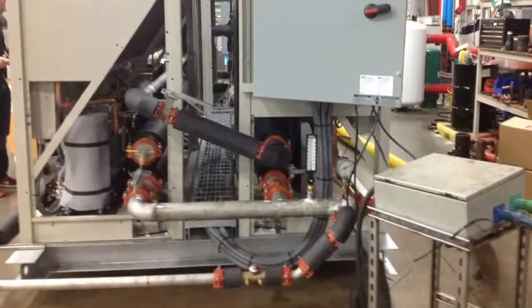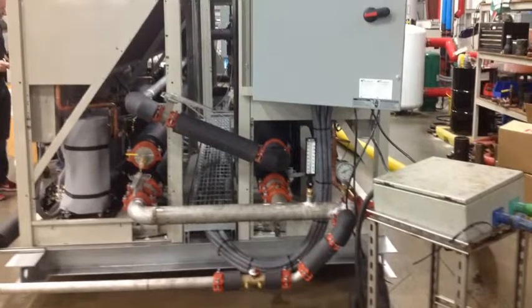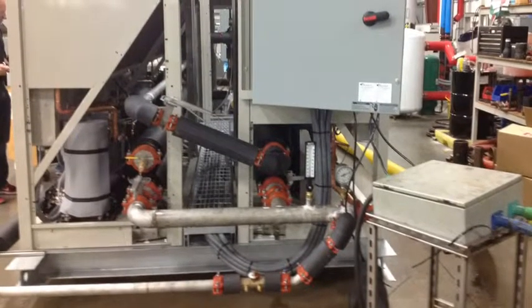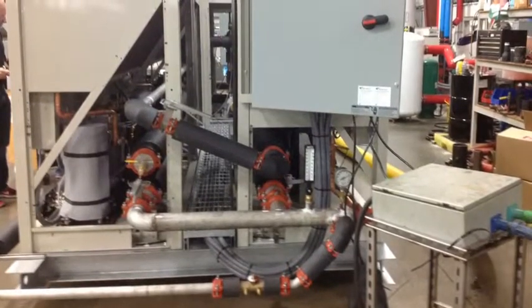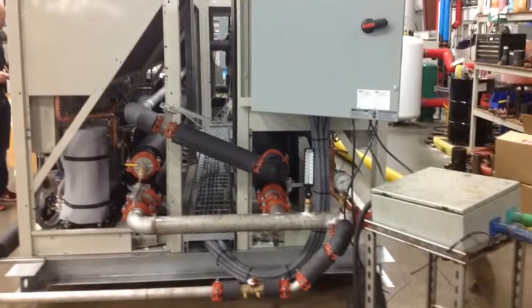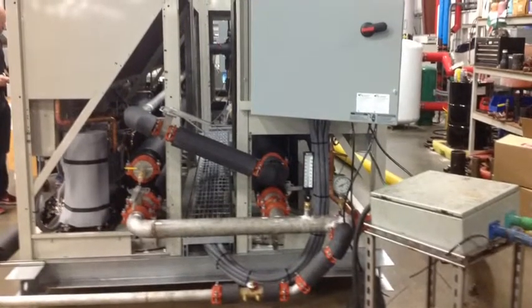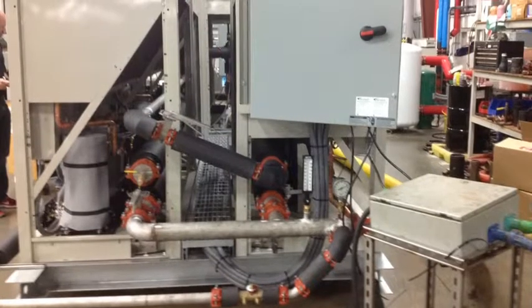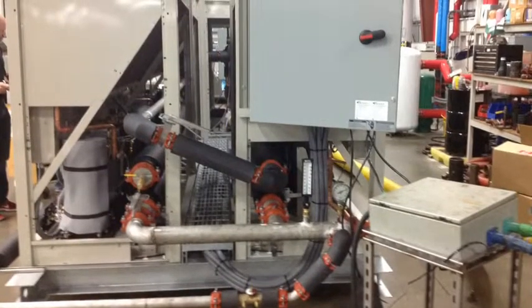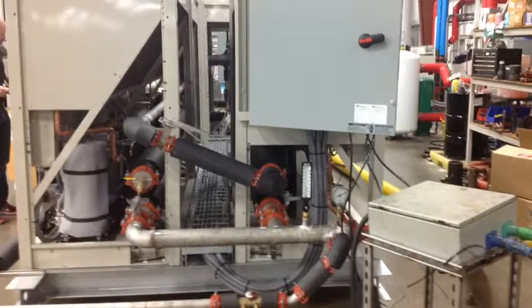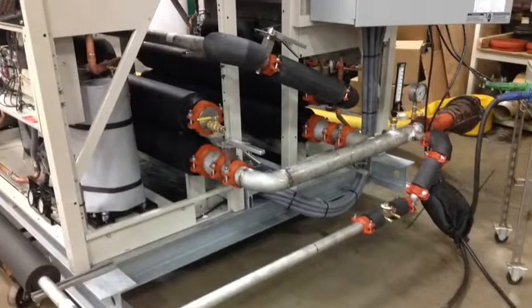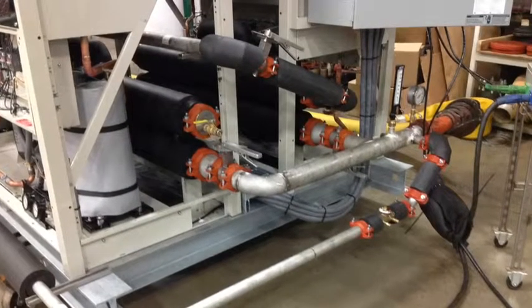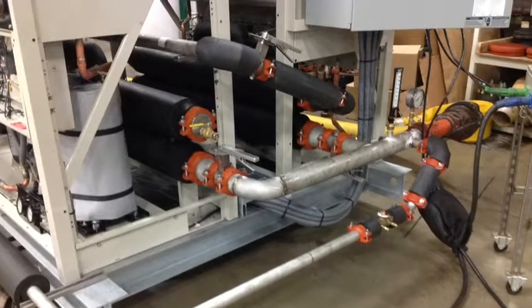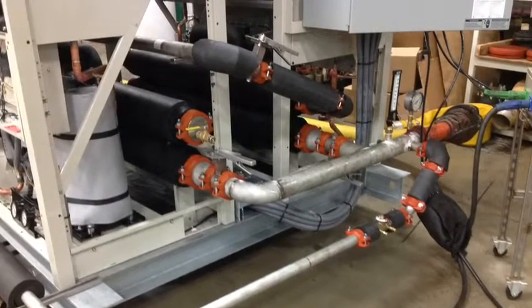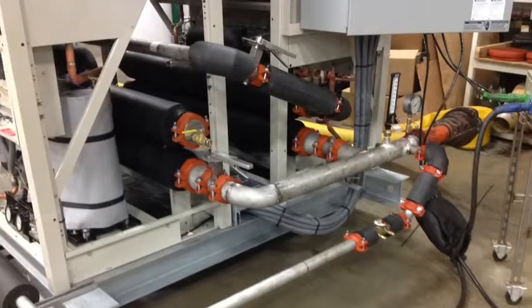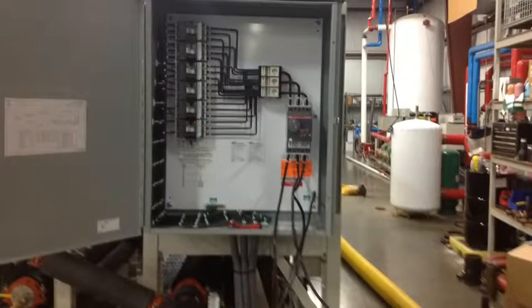As we look at the single point power junction box end of the chiller, you can see the diagonal pipe running from the upper left to the lower right. That is the bypass line that allows us to operate the rear module while hydronically isolating the front modules. You'll also note a balancing valve on the discharge connection. This, used in conjunction with the bypass line that routes back to the storage tank, allows us to send only the amount of water needed by the building. The rest of the water in this constant volume chiller can be bypassed back to the chilled water storage tank.